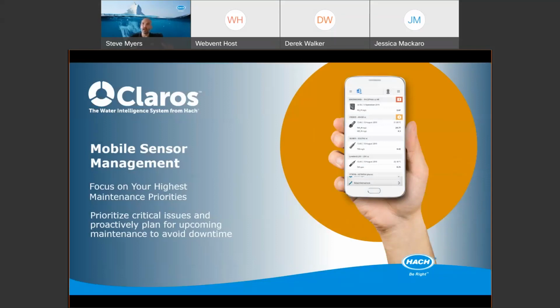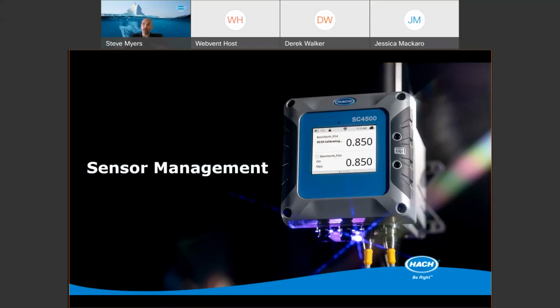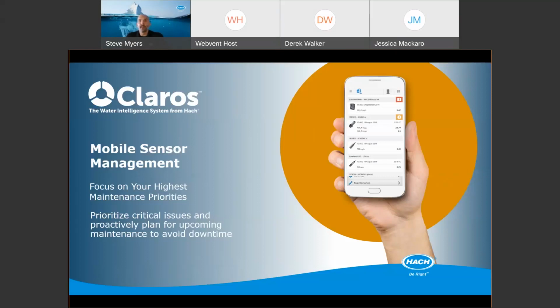So with our controller platform, which the previous slide is a picture of, these sensors all plug into a controller, and that's how we are able to transmit the data back to the SCADA systems, DCS, or other data management systems. We also have built in this ability to bring up what's called our mobile sensor management on our Claros software platform. And what this does is it allows operators and instrument technicians to focus on those highest priority maintenance activities first. So this will give easy step-by-step directions, as well as proactive and time-based alerts for specific maintenance procedures to take place to ensure that your instruments are up and running with high accuracy as much as possible.